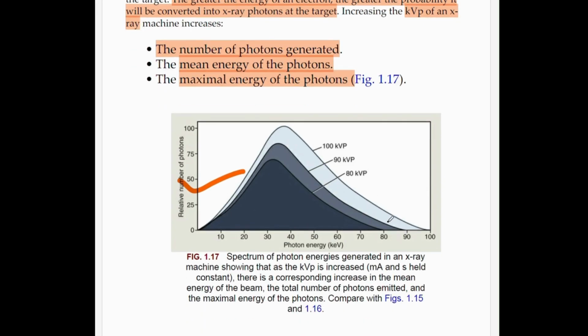What is it showing? This graph, the spectrum of photon energies generated in an X-ray machine, shows that as the tube kilovoltage is increased, this is 80, 90 and 100, there's a corresponding increase in the mean energy of the beam, the total number of photons emitted and the maximal energy of the photons. Increase in the mean energy, number of photons and the maximal photons.